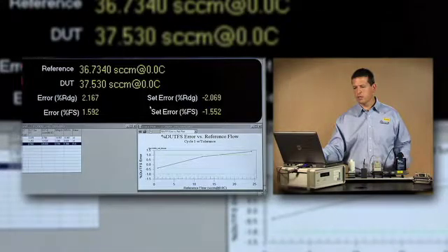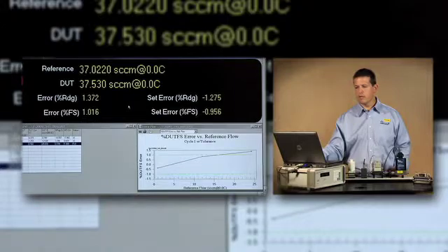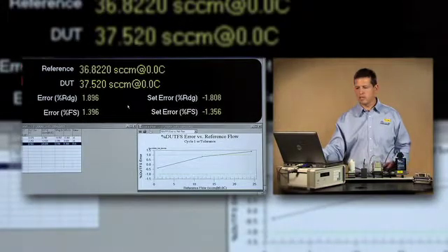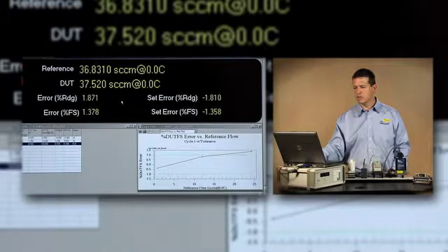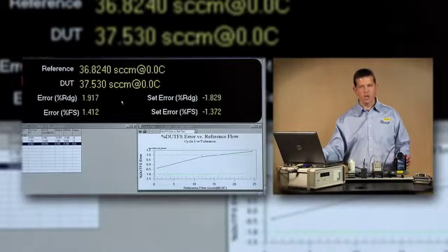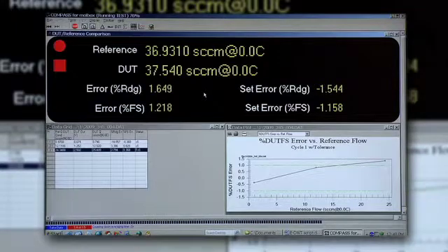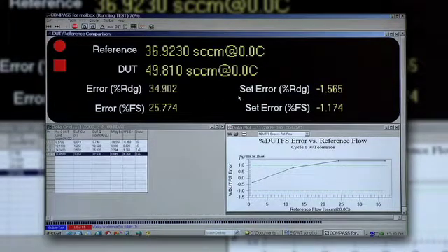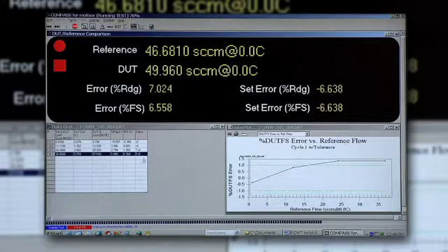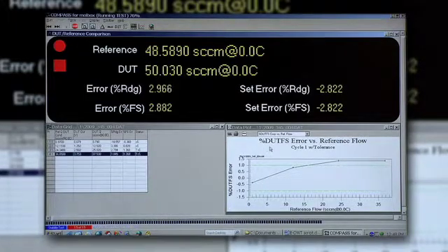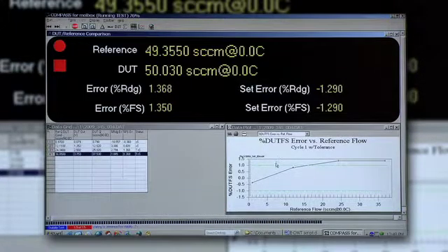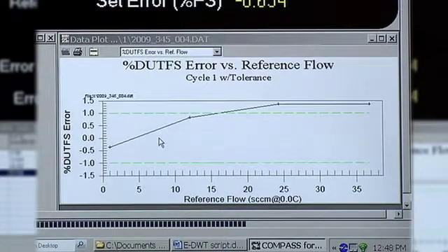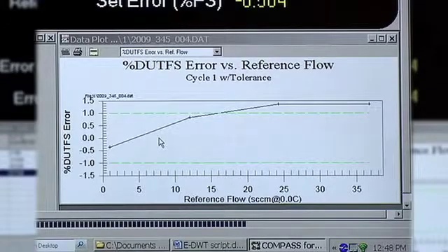With mass flow controller calculations, some customers would like to see an error related to the output of the device under test relative to the measurement output of the reference. And in some cases you'd prefer to see how well the item sets flow with respect to the set point signal that was sent to it, and that would be the set error. In our case we're using the error and that's what's being both recorded here and shown in the plot in the lower right hand corner. On this plot you can see error bands of plus and minus one percent full scale indicated by the dashed green lines.